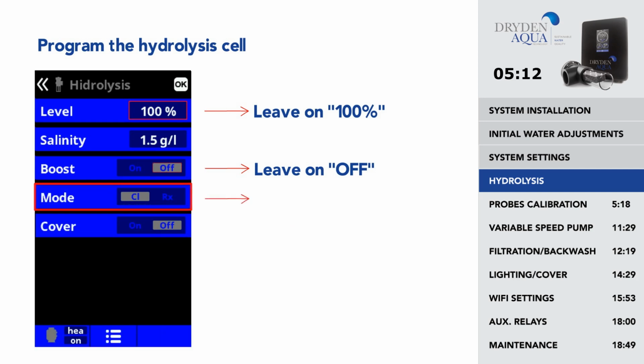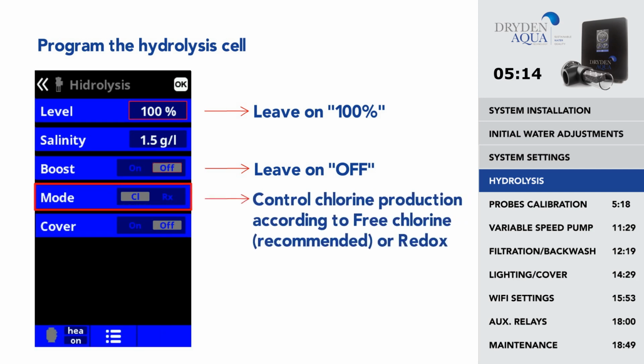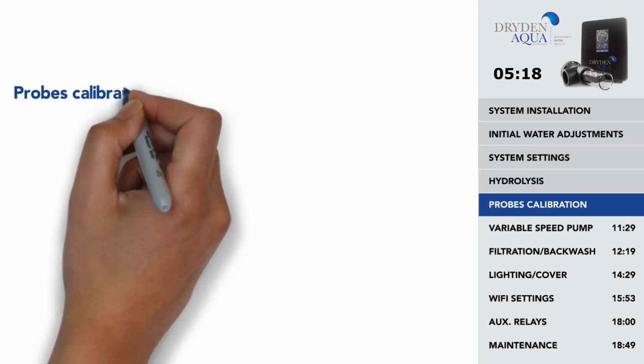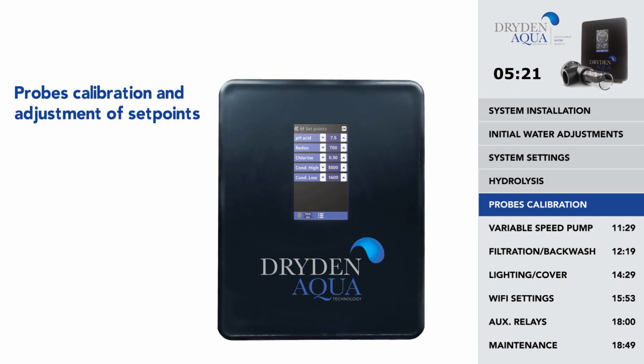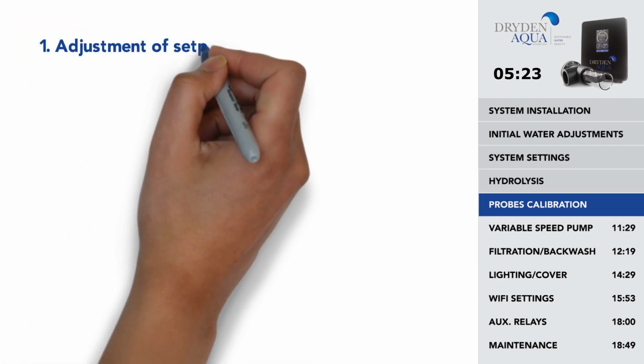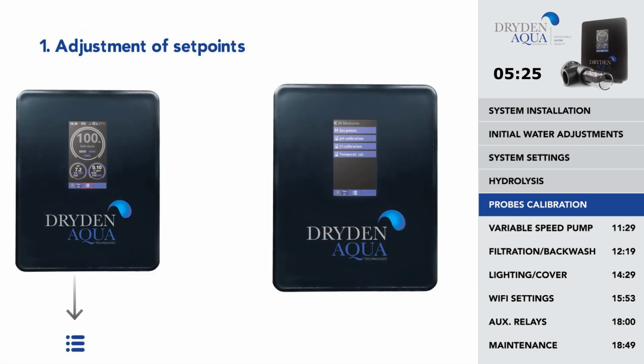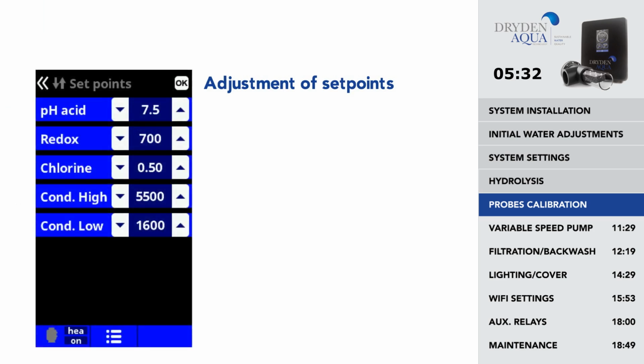You can choose here the parameter that controls the cell's chlorine generation, free chlorine or redox. Probes calibration and adjustment of set points. To adjust all the set points, go to the main menu, press on Measures, and then on Set Points. Adjust set points as follows using the up and down keys.